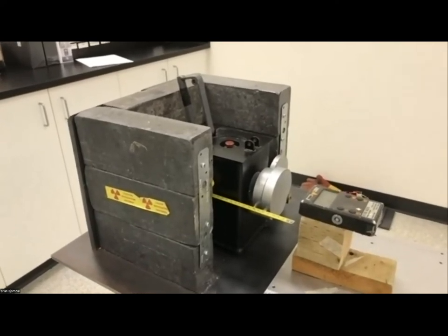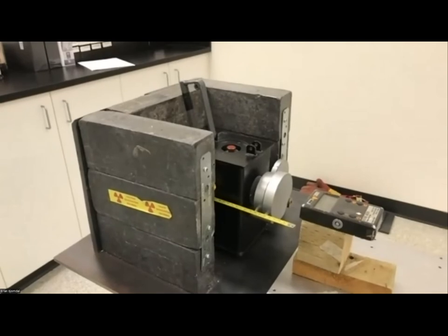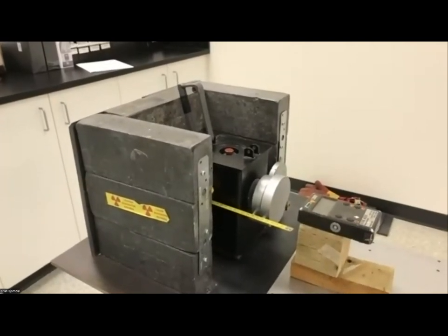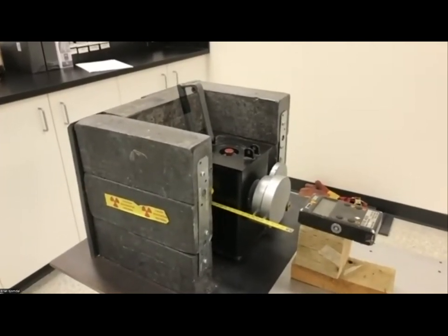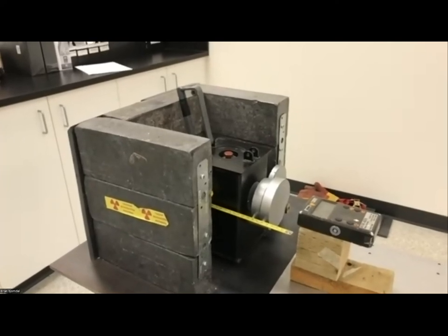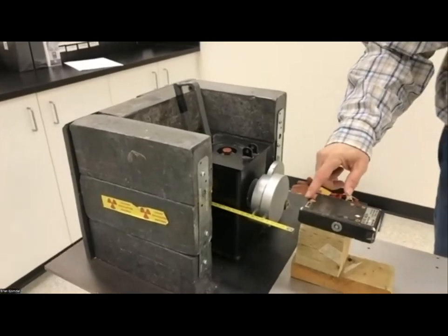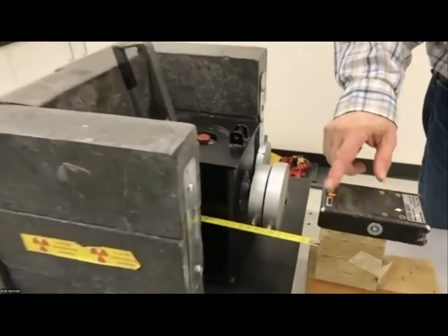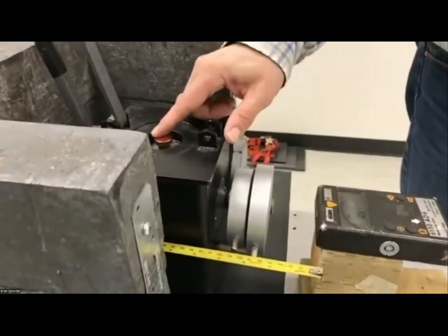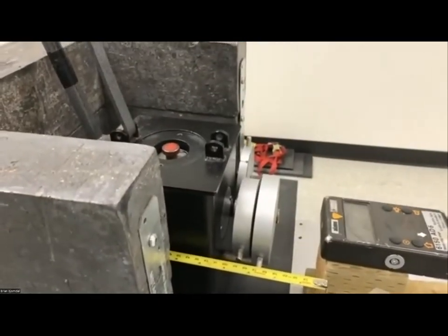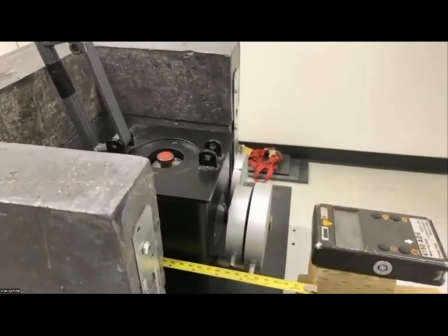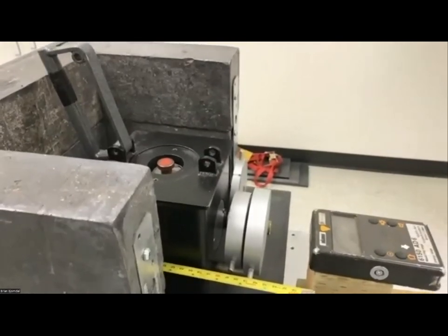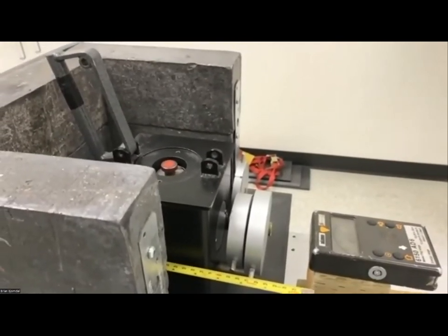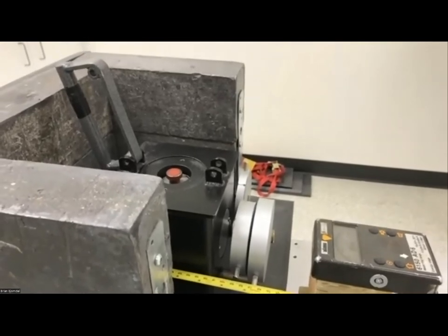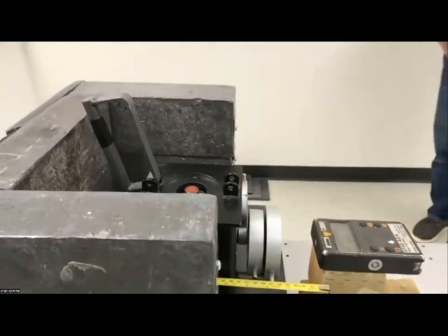Size, you want it to be equivalent to a point source. These sources on the cesium, they're tiny little pellets on the bottom of the source. So generally it shouldn't be an issue. And even the probes in these detectors are quite small. So I don't think there's an issue in terms of the 5 times, if you're talking about the detector or the source. Okay. But it should never be an issue. And then is the plus or minus 20% including or excluding the measurement uncertainty? That would be including the measurement uncertainty. So it should perform to within 20%.